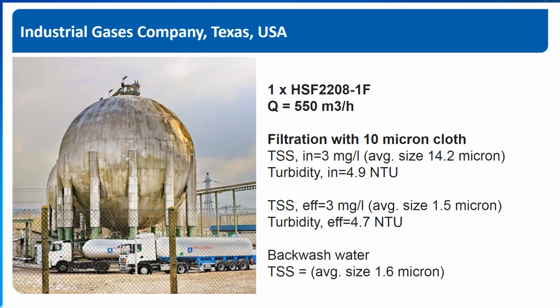Right. Okay, I think that's a good question. Actually, this is what we typically see at a well-functioning site. What's happened here is that at the time of the sample grabbing, the cooling tower and the side stream filter had reached a steady state, meaning that there hadn't been an infiltration of dust or any contaminants in the short term. So the filter had reached a point where basically it was just maintaining a level of TSS in the water at around 3 milligrams per liter. But you could see from the size of the solids that were coming in at around 14 micron, and the size of the ones that were coming out at 1.5 micron, that it was actually removing most of the solids that were in the system.